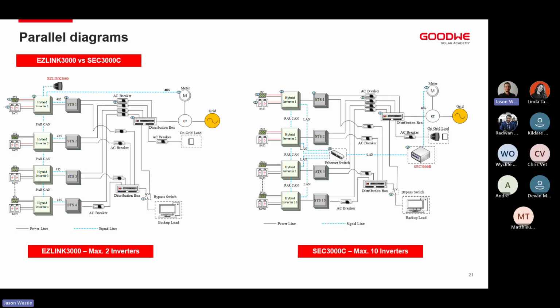Another thing about our SEC3000C controller is that we can add additional grid-tied inverters onto a system. So if you have a massive plant, we've got an example of one of these where we've got a 1.2 megawatt grid-tied system running their main factory, and they've got 400 kilowatts of backup running one of their smaller factories on the same premises. We have got everything connected to this one SEC3000C controller, meaning that wherever we clamp on our CT side, the PV from both departments or both sections, grid-tied and non-grid-tied hybrids, can be joined together, and that power can be distributed evenly across all of them. So when we do this using the SEC3000C controller, we can parallel up to 60 grid-tied inverters, and then up to 10 hybrid inverters in parallel as well.